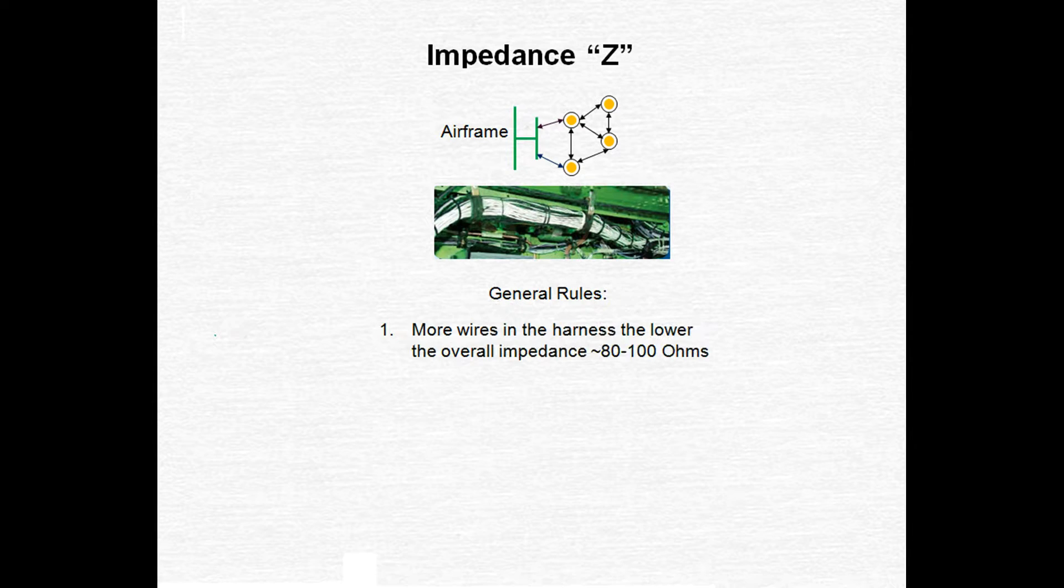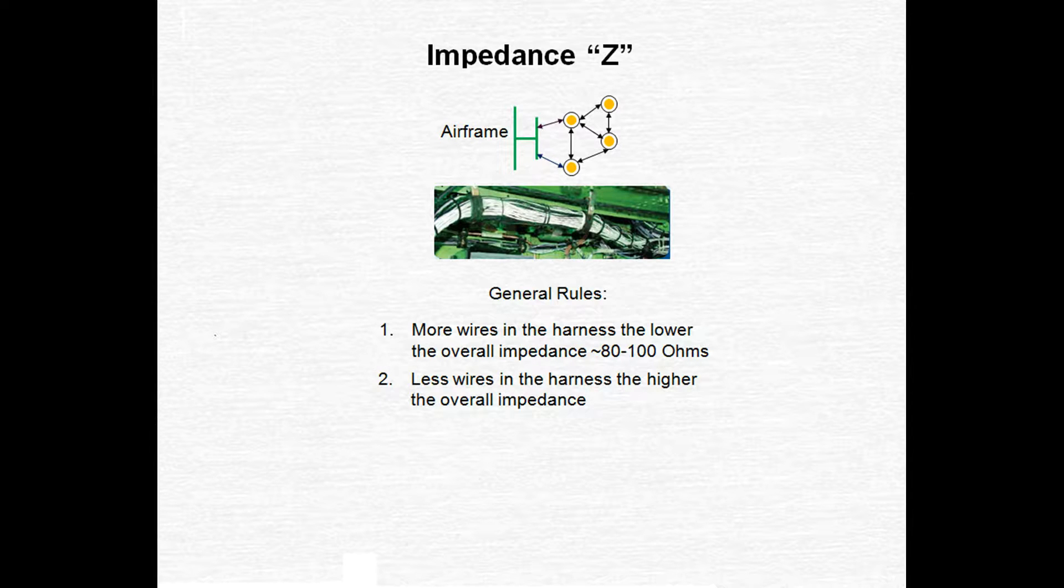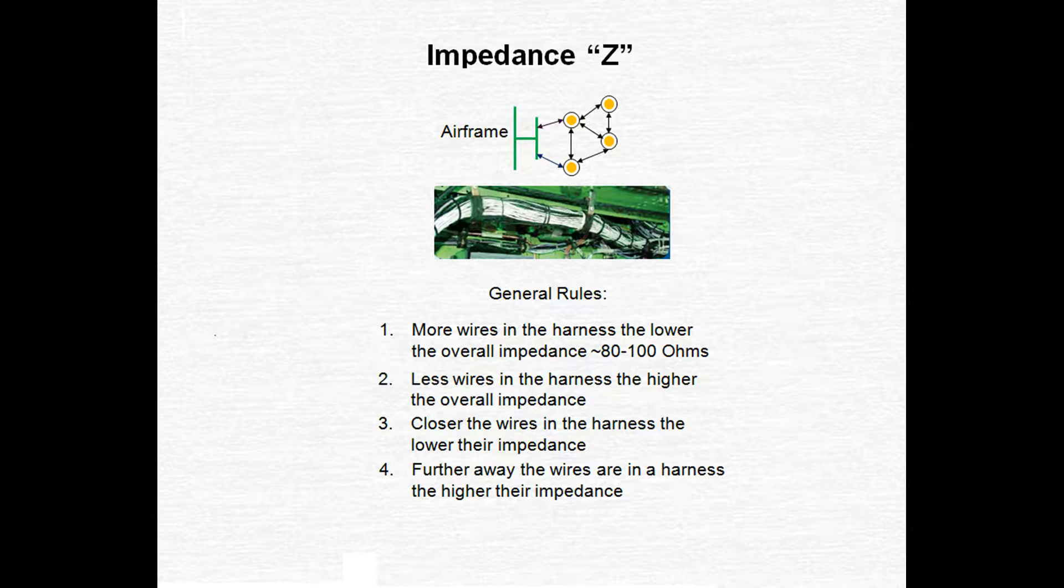So let's throw some general rules out for impedance. More wires in your bundle, the lower your overall impedance will be. And likewise, the fewer wires in the bundle, the higher your impedance will be. Closer wires result in a lower impedance. Wires further apart result in a higher impedance. And finally, these rules apply to any wire or airframe that's next to the wire you're measuring.